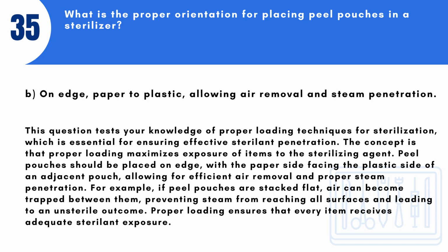For example, if peel pouches are stacked flat, air can become trapped between them, preventing steam from reaching all surfaces and leading to an unsterile outcome. Proper loading ensures that every item receives adequate sterilant exposure.